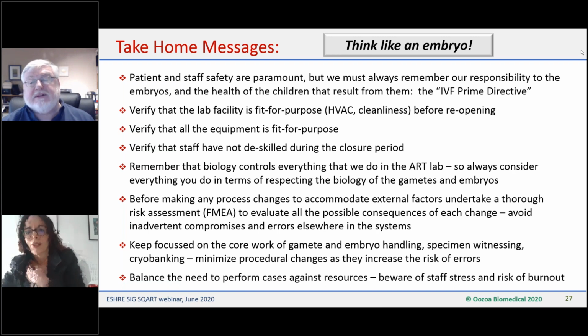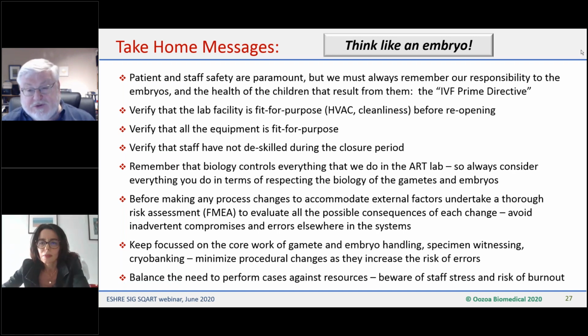But tank cleaning is something that many places do or are expected to do. With high security straws, it's not necessary, but you will have that sludge at the bottom of the tank. And if a tank is old, it will probably have quite a lot of that stuff down the bottom. And you mentioned the cleaning with peroxide. There is a question here asking what percentage of peroxide we should use for the cleaning? Hydrogen peroxide, use 6%. 6%, right. That's the standard stuff to use, and wear gloves while you're using it.